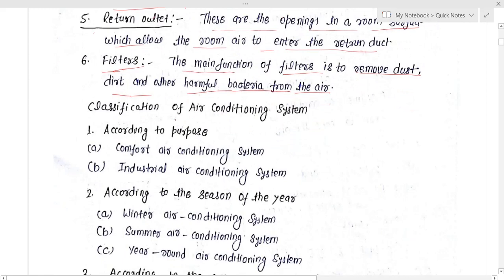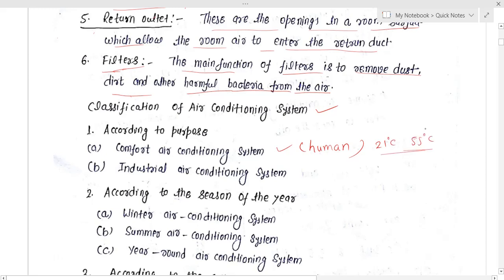The air conditioning system is classified in three ways. According to purpose, either we design the system for comfort air conditioning — that is, for human beings. The condition of comfort air conditioning requires a temperature of nearly 21 to 22 degree centigrade and a relative humidity range of 50 to 60 percent.